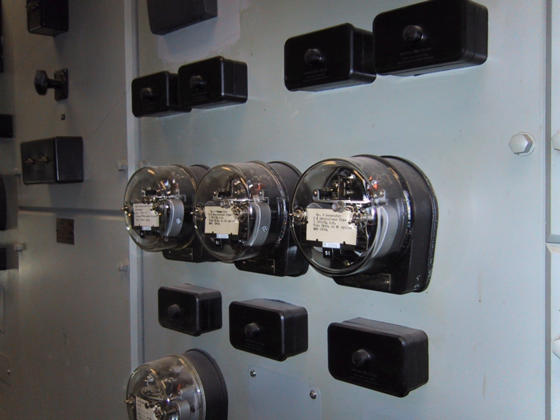electromechanical relays. Electromechanical relays provide only rudimentary indication of the location and origin of a fault. In many cases, a single microprocessor relay provides functions that would take two or more electromechanical devices. By combining several functions in one case, numerical relays also save capital cost and maintenance cost over electromechanical relays. However, due to their very long lifespan, tens of thousands of these silent sentinels are still protecting transmission lines and electrical apparatus all over the world.